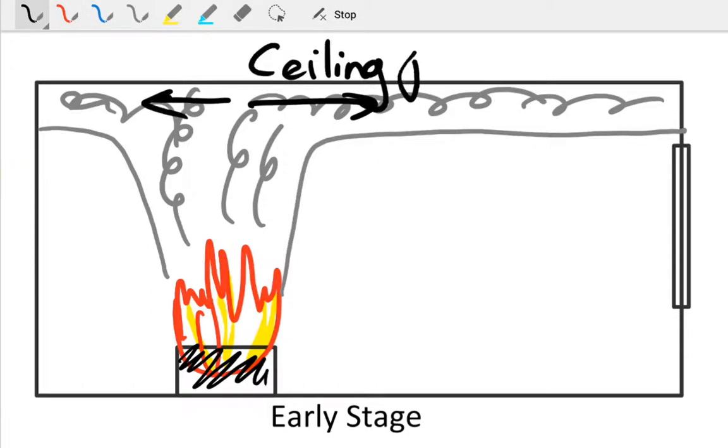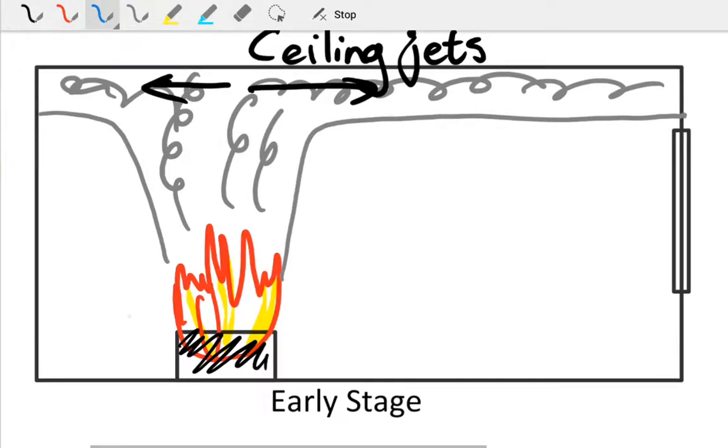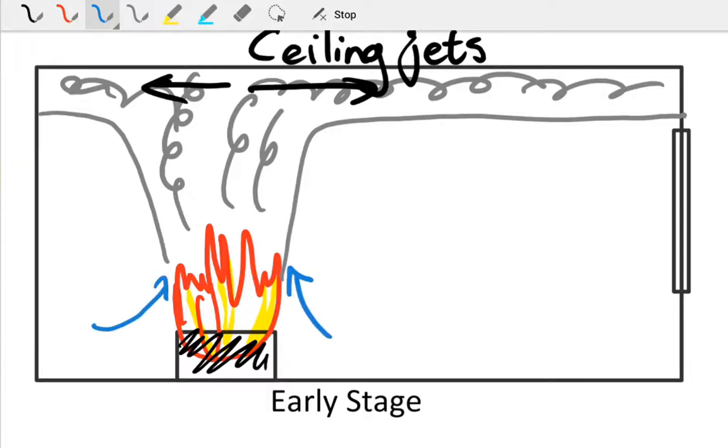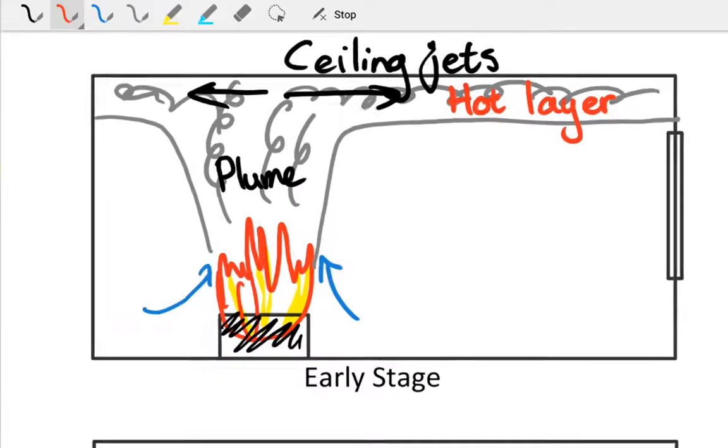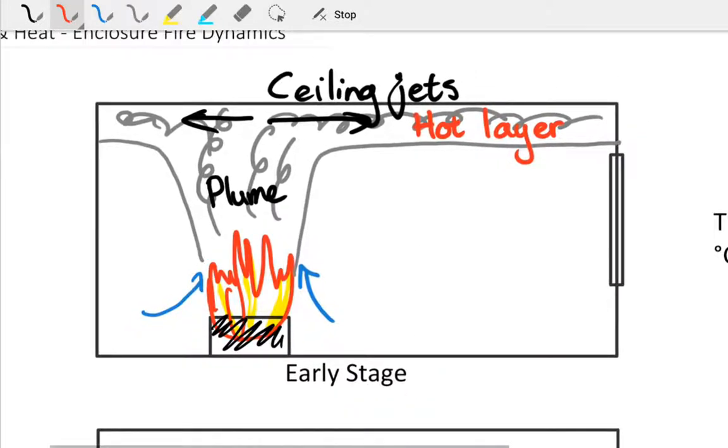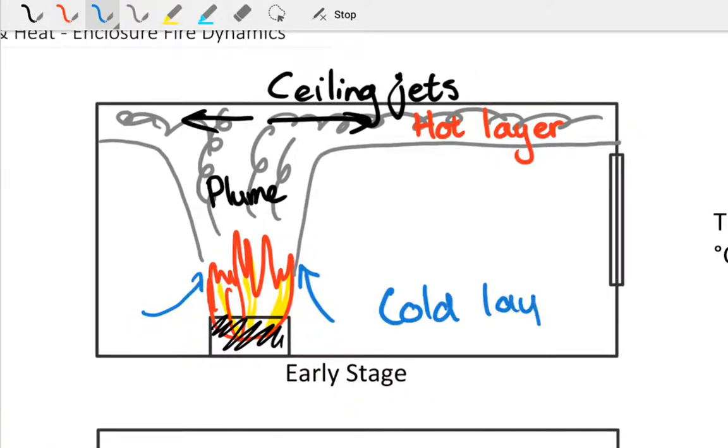As it burns, there is more than enough oxygen available. It's just a package burning in the room, so we've got air entrainment from either side of cooled air and the plume. There's our smoke plume in the middle, and this causes the hot layer at the top to build up. So there's our hot layer, and then at the bottom we have our cold layer of just ambient temperature air around the fire.